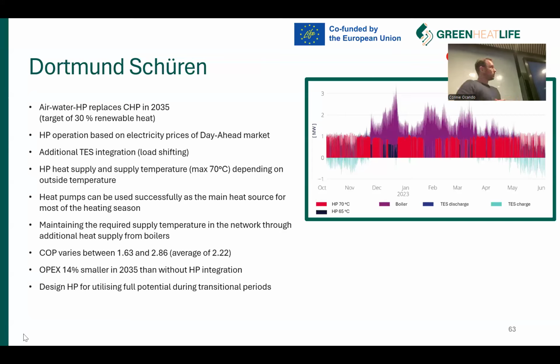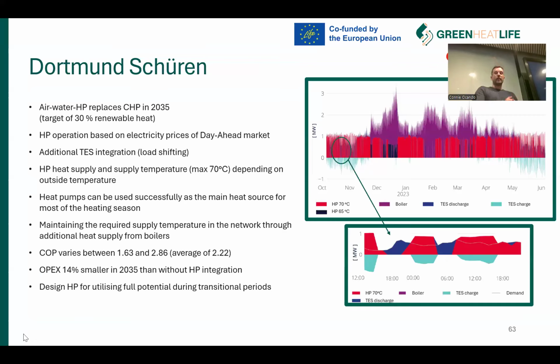Therefore, we also want to integrate a thermal energy storage for load shifting. So we want to operate the heat pump at maximum load, for example at 1 megawatt. And if the demand is not as high as the nominal capacity of the heat pump, we can then charge the thermal energy storage. Some hours later, when the electricity price rises, we shut off the heat pump, but we have the storage loaded, so we can discharge it. So we operate the heat pump at the most beneficial electricity price, but also at full load, not in part load, which is not as efficient as the nominal load.